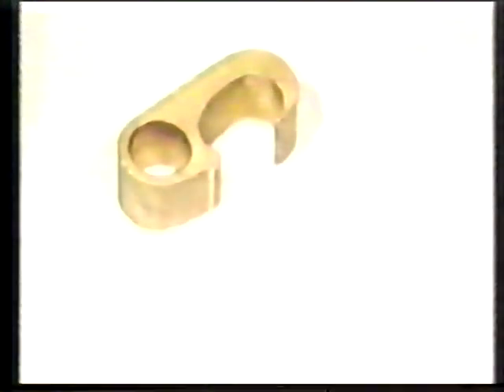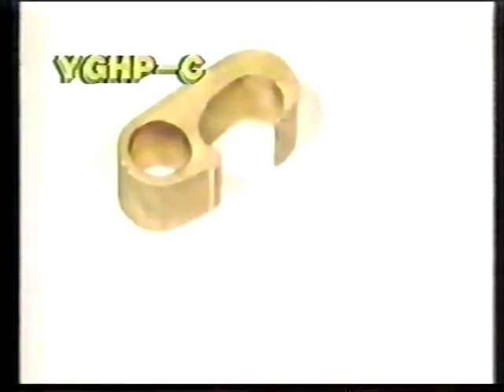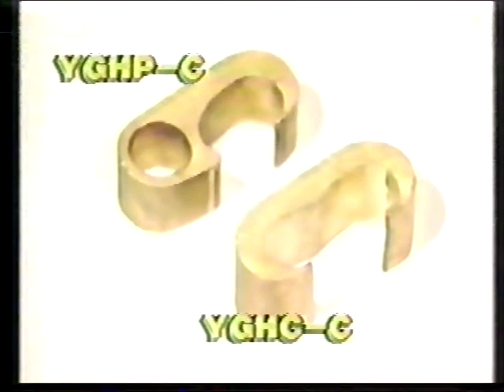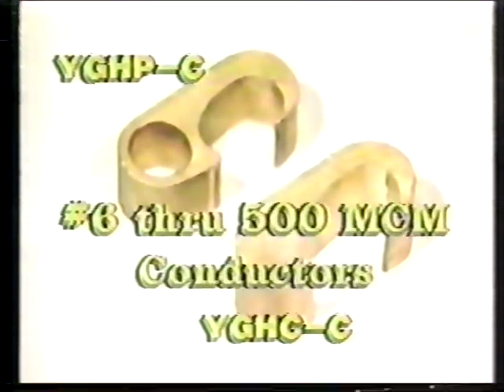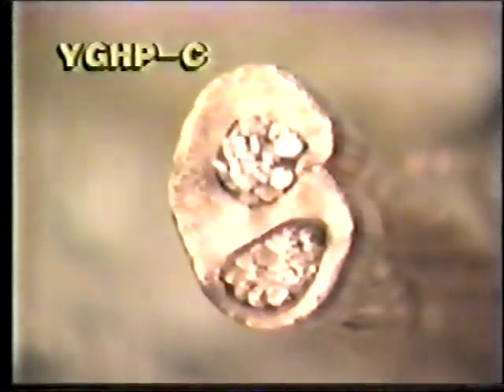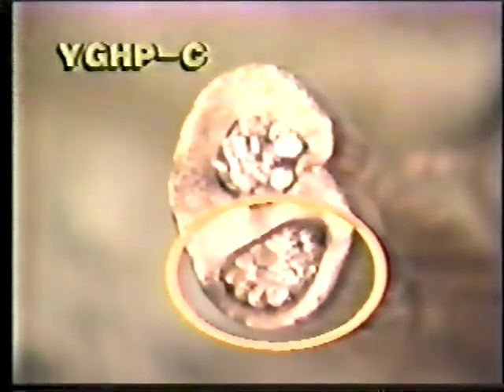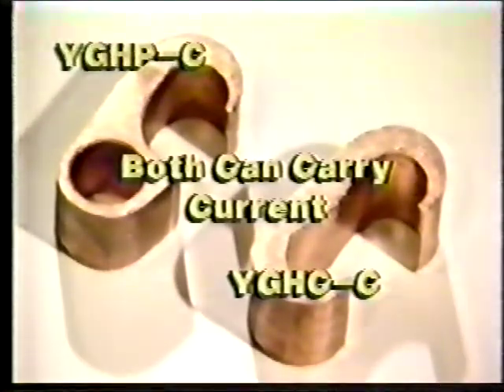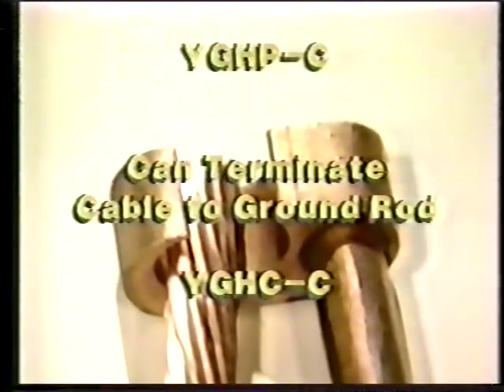Burndy's HYGROUND compression system provides 2 types of tap connectors, the heavy-duty figure 6 construction and an economical open C design. They're both range-taking and available to accommodate conductors from number 6 through 500 MCM. The figure 6 design, however, has the added benefit of containing the individual strands of the tap cable for a more consistent installation. Since they both meet UL and IEEE requirements, the one to use depends on the design preference or the specifying engineer. Please note that both of Burndy's tap connector designs can be used for current carrying applications, and the figure 6 model can be used for terminating a cable to a ground rod.